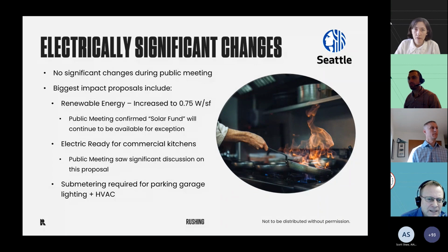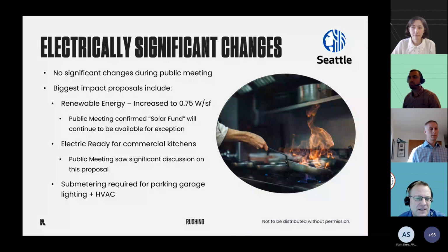Electrically, one more item that's a bit of an expansion for energy monitoring is additional sub-metering for parking facilities, specifically for the lighting and ventilation spaces. One clarification from this past week's public meeting was that this applies to garage space only, not spaces within the garage. So if you've got an elevator machine room with a fan coil and a split system, it's not talking about that split system, just the larger equipment serving the garage itself.